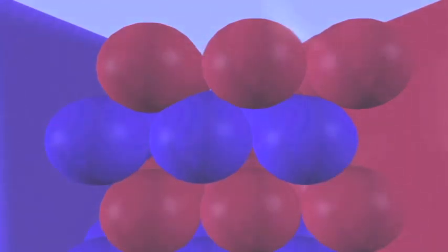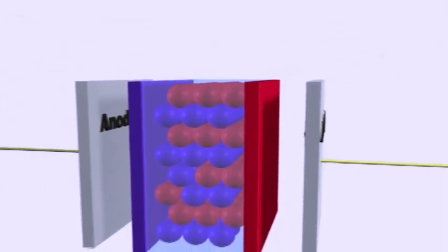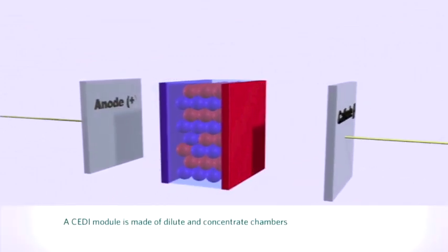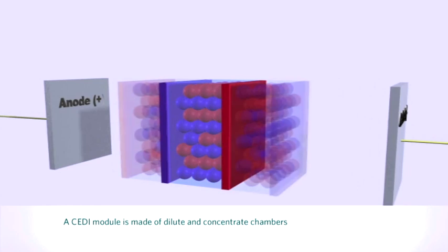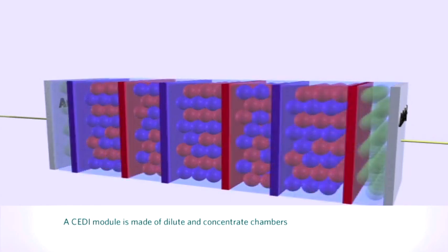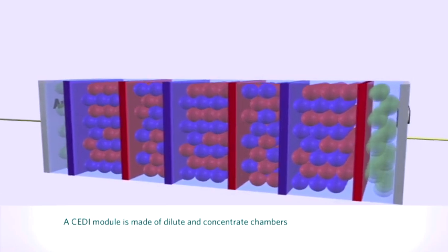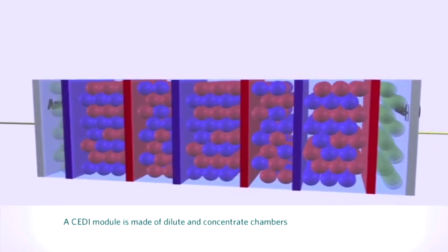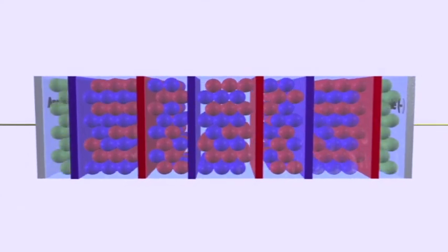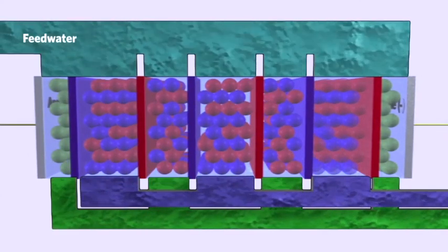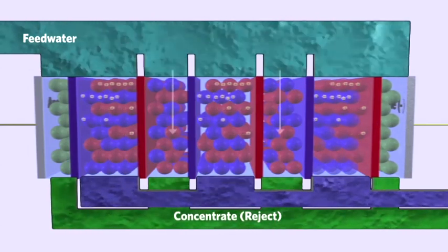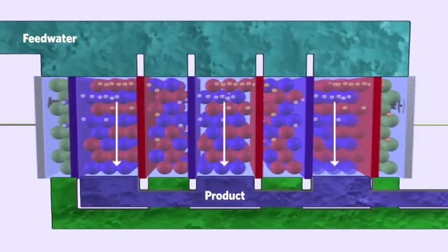Taking a step back to look at how an IonPure CEDI module is constructed, we can see that if we move the electrodes farther apart and continue to add resin beads sandwiched between the cation and anion-selective membranes, we create a series of water purification compartments alternating with compartments where the ions are concentrated. As feed water is pumped into the system, it is diverted into separate compartments, mainly the concentrating compartment and the purification or dilute compartment.